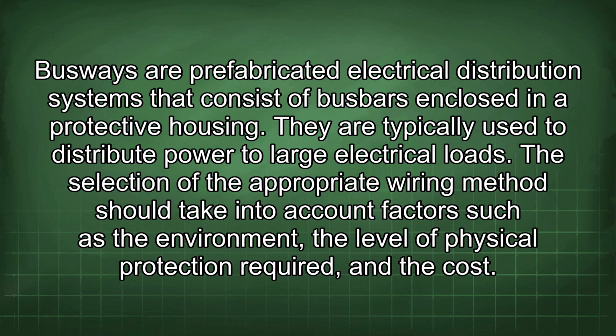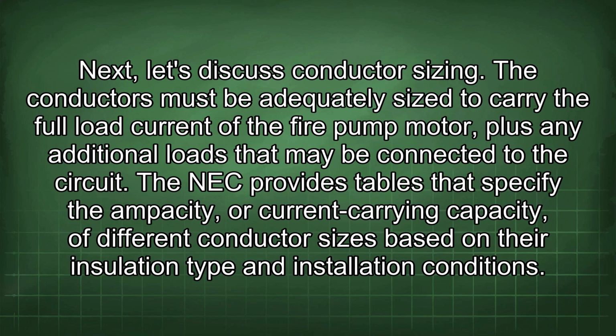The selection of the appropriate wiring method should take into account factors such as the environment, the level of physical protection required, and the cost. Next, let's discuss conductor sizing. The conductors must be adequately sized to carry the full load current of the fire pump motor, plus any additional loads that may be connected to the circuit.